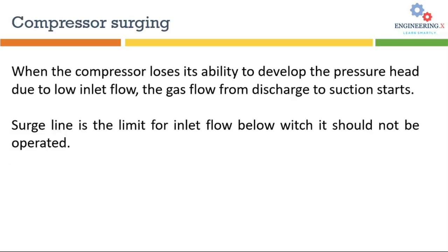So first, what is compressor surging? When the compressor loses its ability to develop the pressure head due to low inlet gas flow rate, reversal of gas flow from the discharge side to the suction side starts, and this condition is called surging. The surge point is the minimum limit of inlet flow rate for a centrifugal compressor, below which it should not be operated.